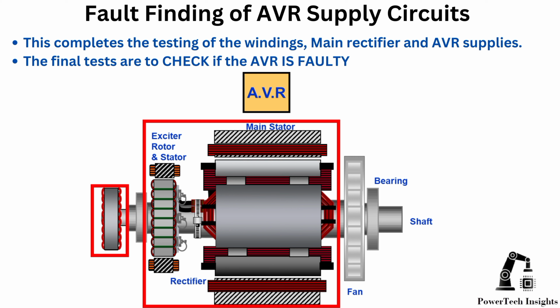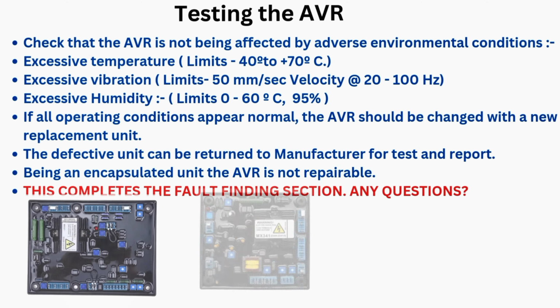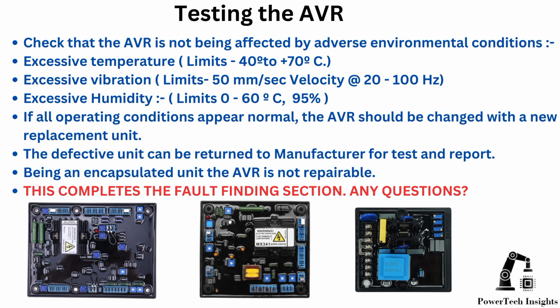The final test is to check if the AVR is faulty. Testing the AVR. Check that the AVR is not being affected by adverse environmental conditions. Excessive temperature limits: minus 40 degrees to plus 70 degrees C. Excessive vibration limits: 50 mm/sec velocity at 20 to 100 Hz. Excessive humidity limits: 0 to 60 degrees C, 95%.